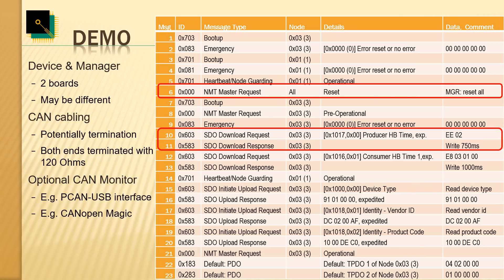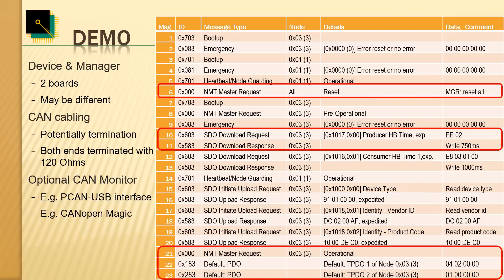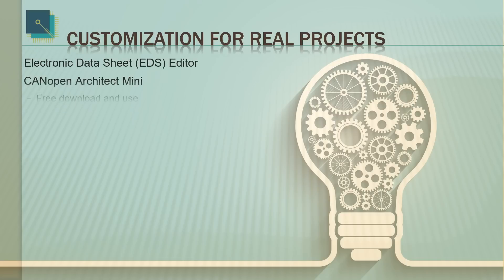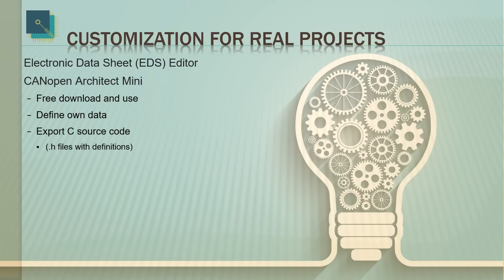There are several more SDO requests back and forth between the manager and device node 3, until line 21 where we see another Network Management master request — the command to node 3 to switch into operational mode. This means it will start transmitting process data from then on, and on lines 22 and 23, as a result of that request, node 3 starts transmitting the process data. To simplify customization, we provide an Electronic Data Sheet (EDS) editor. The EDS is the specification of all CANopen communication and data parameters.